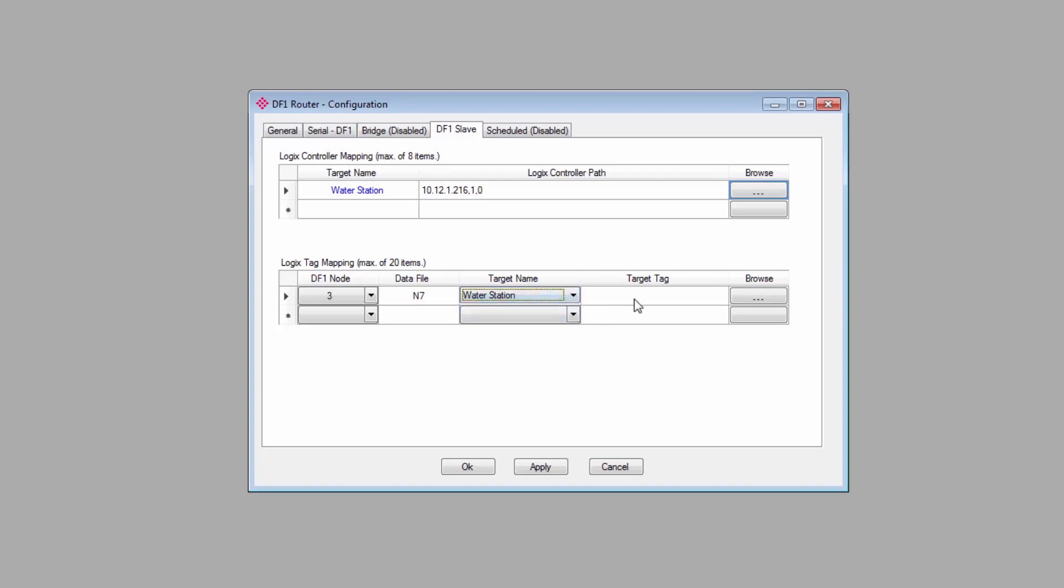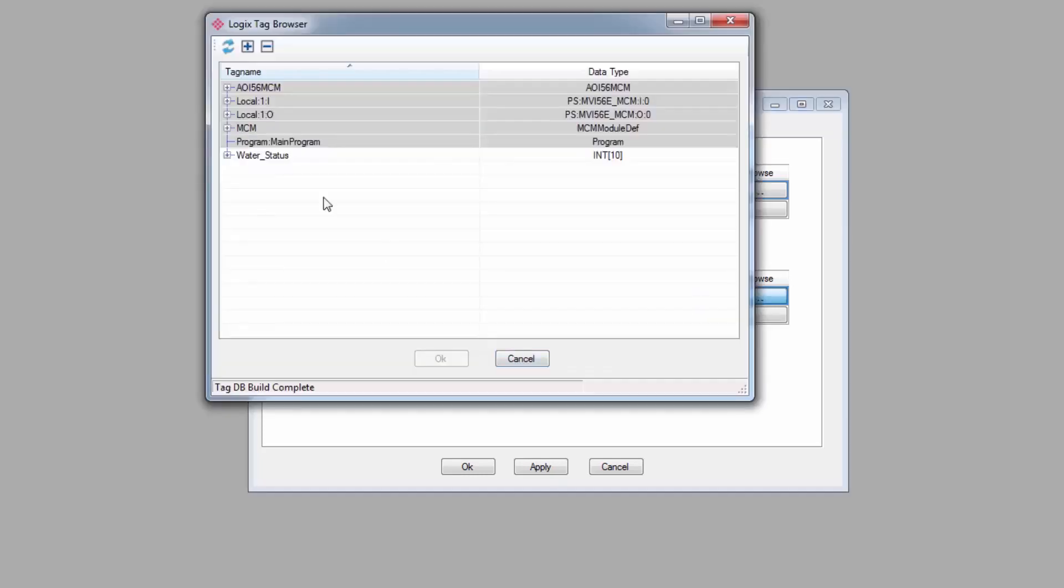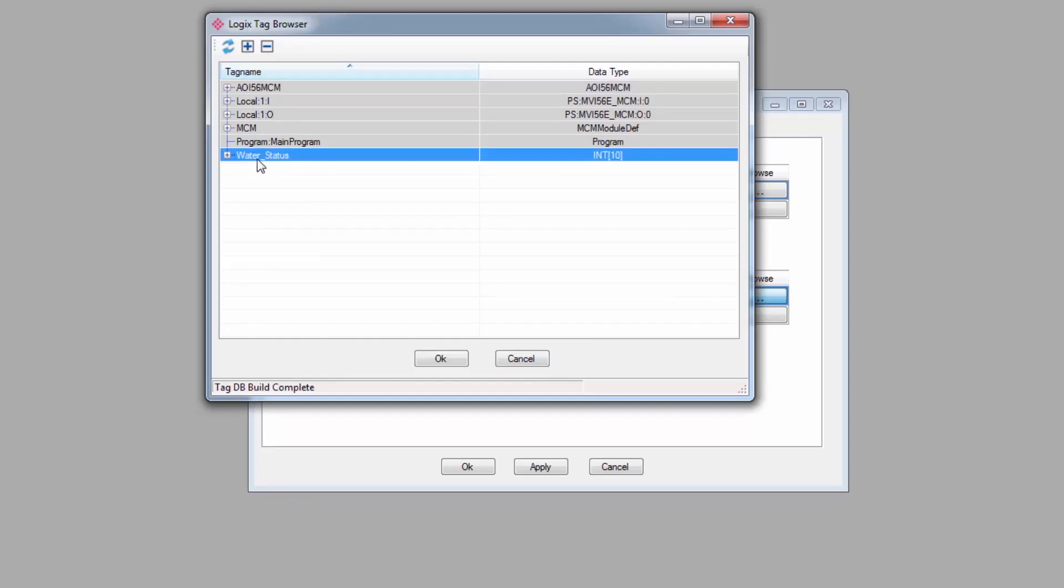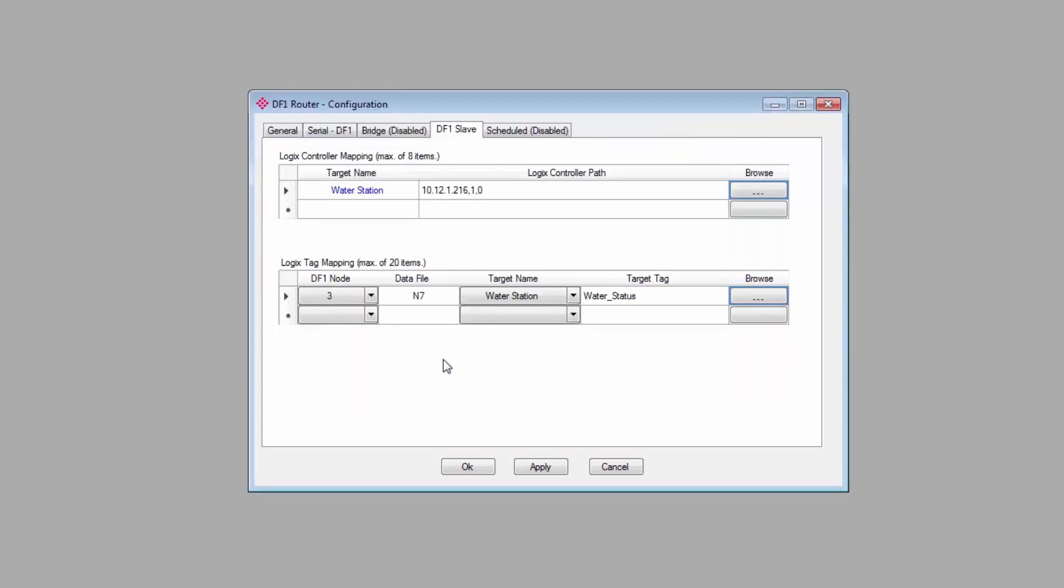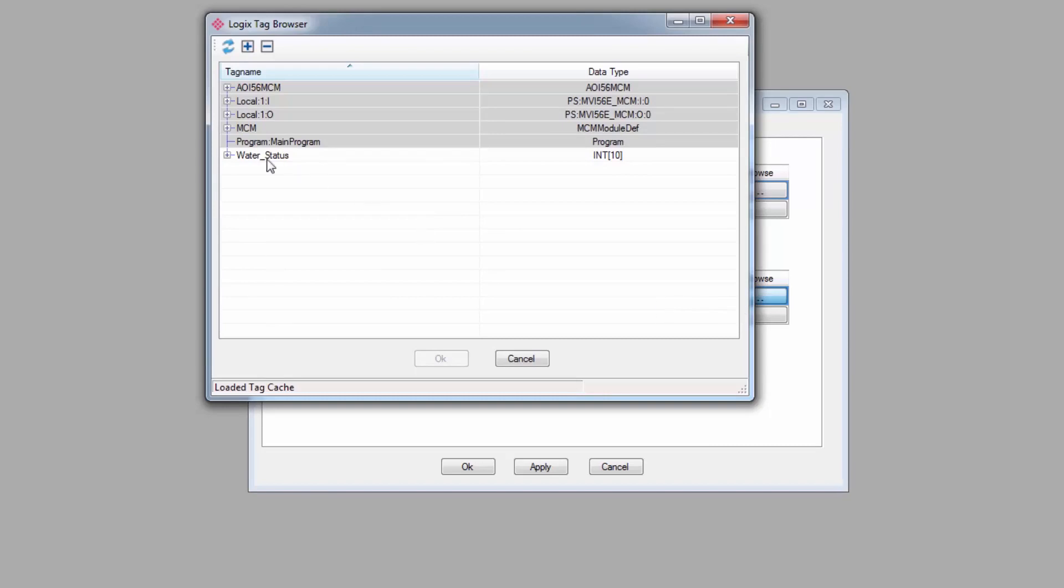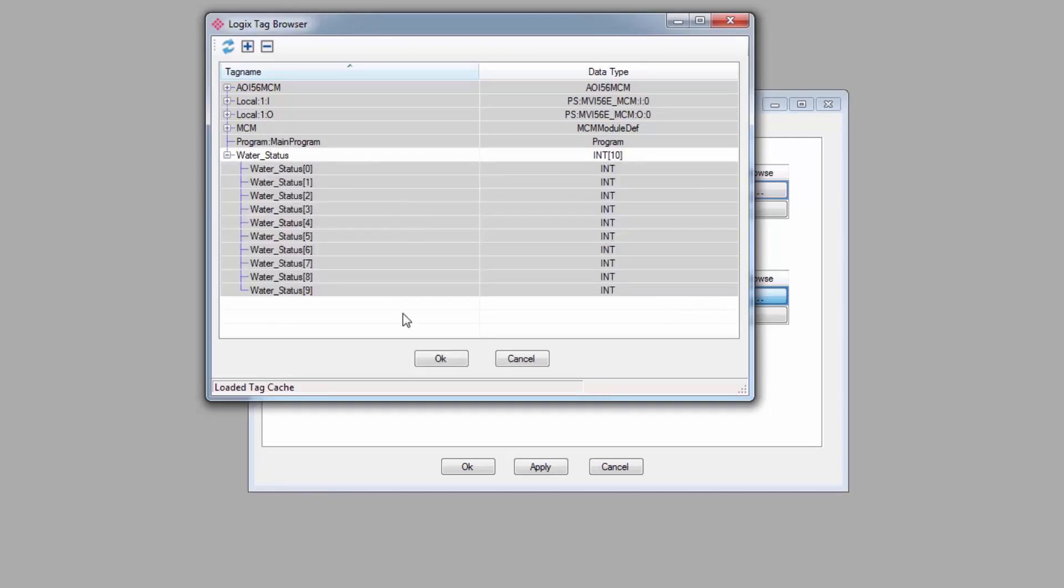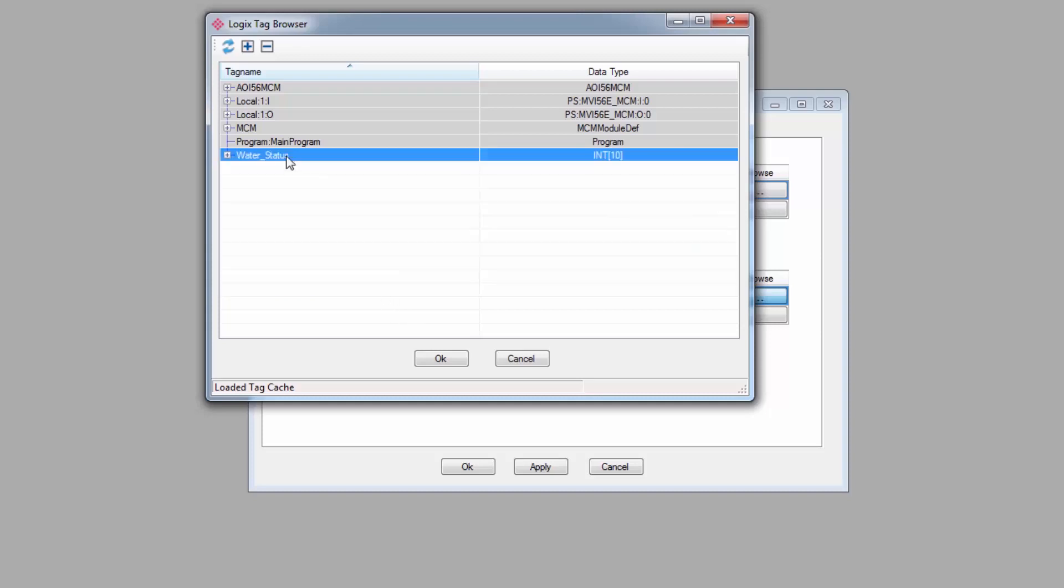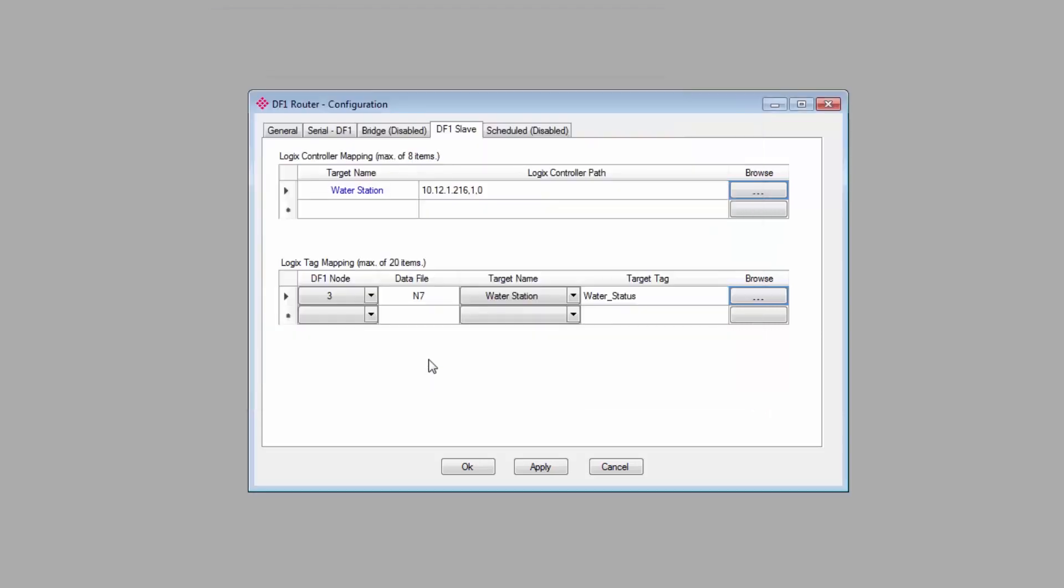The target name corresponds to the Logix controllers identified above. So for me, it's Water Station. And then the target tag is the target controller tag in the Logix controller. So simply click the Browse button, and you can browse your Logix controller and find the appropriate controller tag. If you're not online with the controller, you can also manually enter the tag name. Now, no size is specified here, so you'll need to make sure that the target tag is big enough to satisfy the DF1 message size. In my example, the Water Status tag is an array of 10 integers.